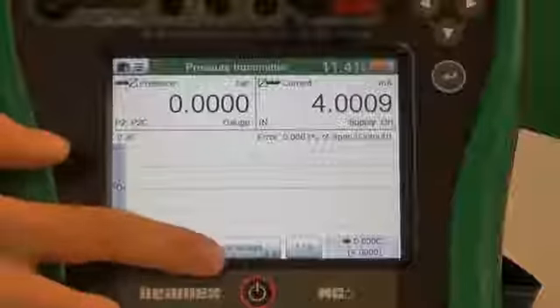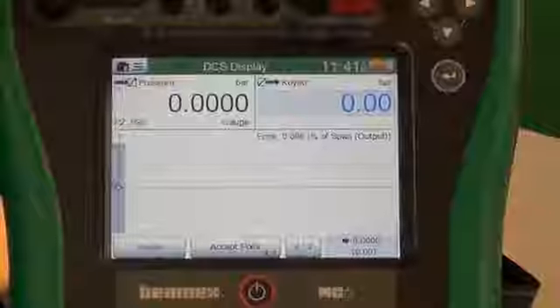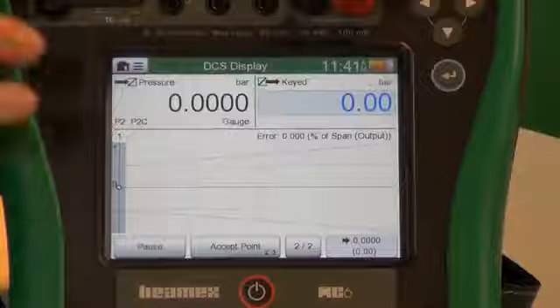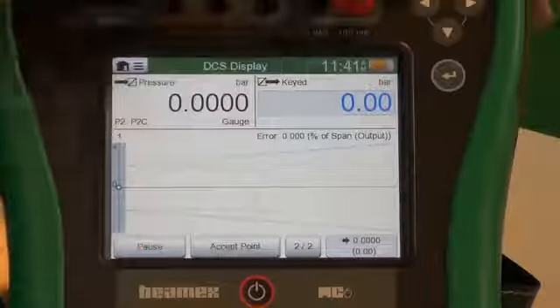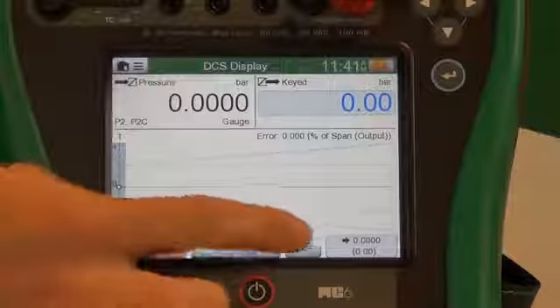As soon as we hit start, the MC6 starts the countdown, looking for 0 bar and 4 milliamps. As soon as it's accepted, it goes to the second instrument in that group.